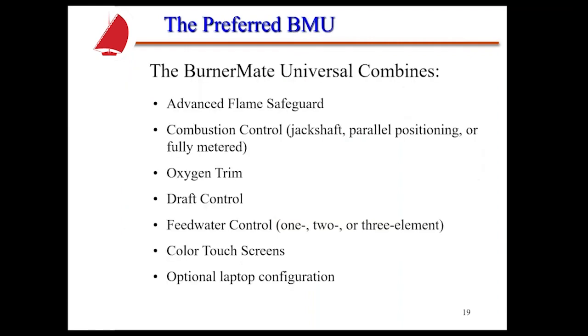And that's what the Burner Mate Universal that we build does. It's got the advanced flame safeguard in it. It's got complete combustion control built in, oxygen or O2 trim built in, draft control built in. All you have to do is buy the end device. Feed water control, which we haven't talked about, can do 1, 2, or 3 element, and it even incorporates a smart feed water control. So it can actually switch down to single element when necessary and when it's the best control scheme. The Burner Mate Universal, or BMU, you also can select touch screens for it, and we have optional laptop configuration. Many systems out there have this kind of capability. We feel that the BMU goes beyond most of those.